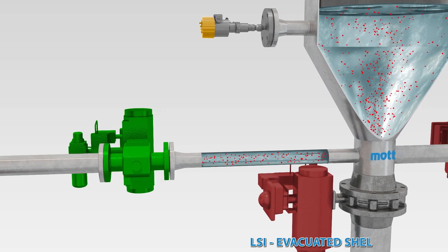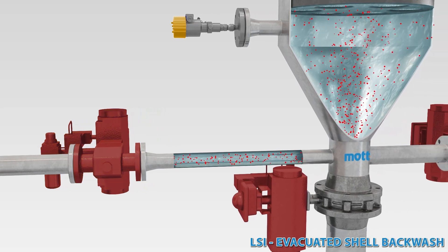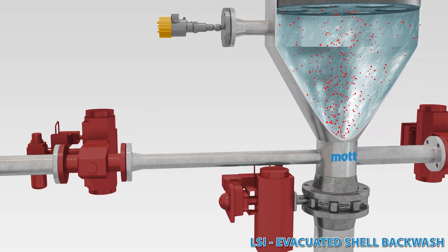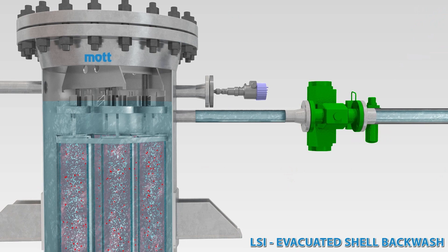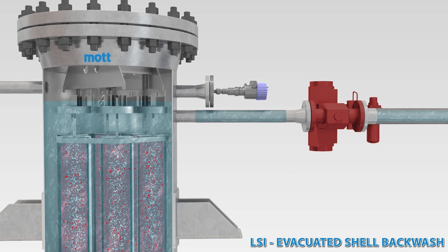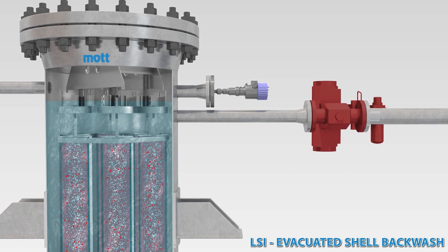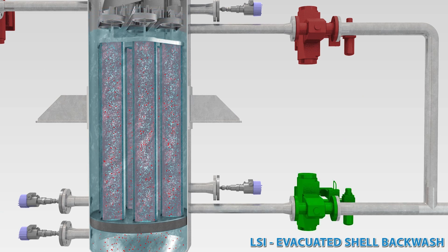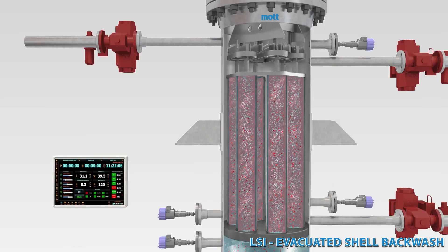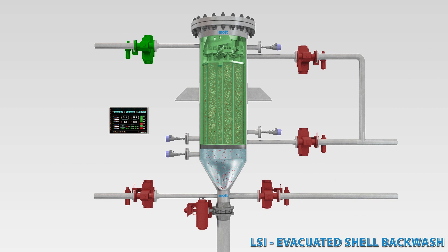To maximize the recovery of filtrate, the evacuated shell backwash may be configured. The vessel is isolated from process inlet and outlet lines. Filtrate is drained through the lower shell drain connection. Pressurized clean gas is charged to the filter vessel shell until the backwash pressure set point is reached.